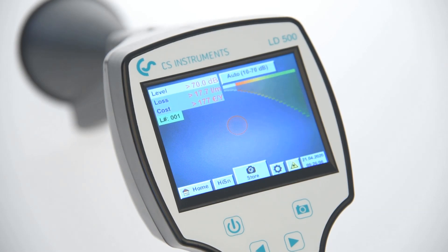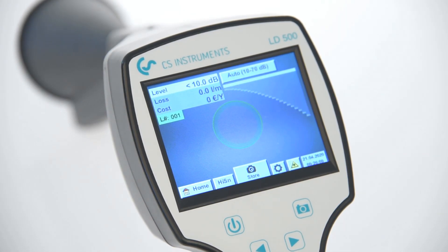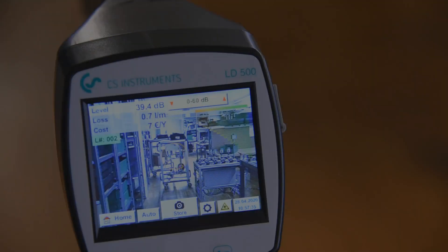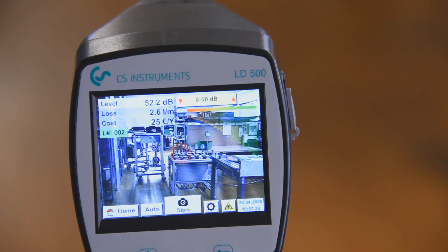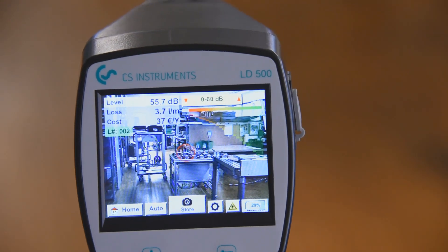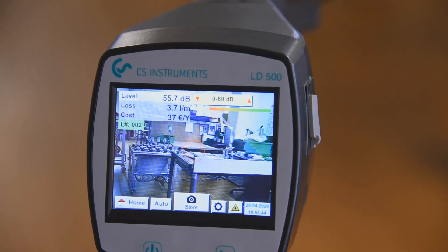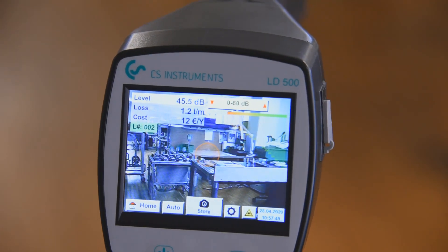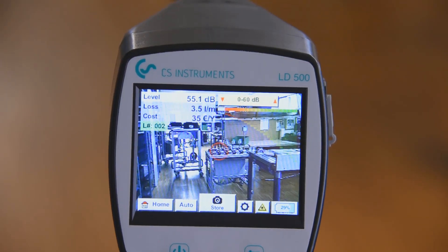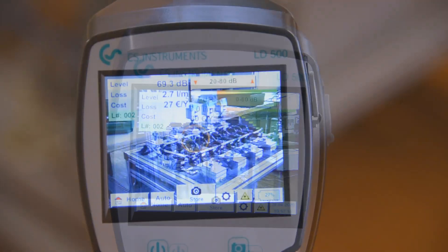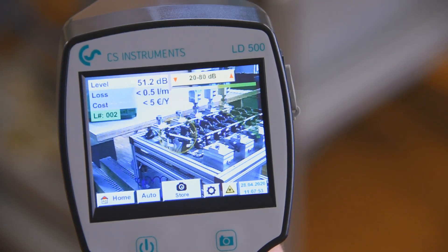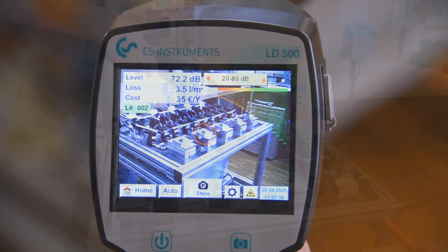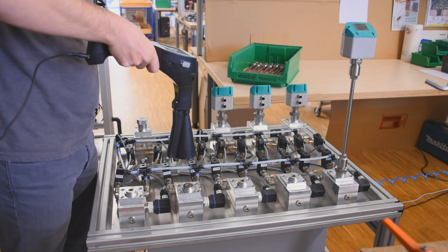The color and size changing circles in the middle of the screen make it easy to locate and zoom in onto an existing leak. Alternatively, the compressed air system can be scanned systematically.